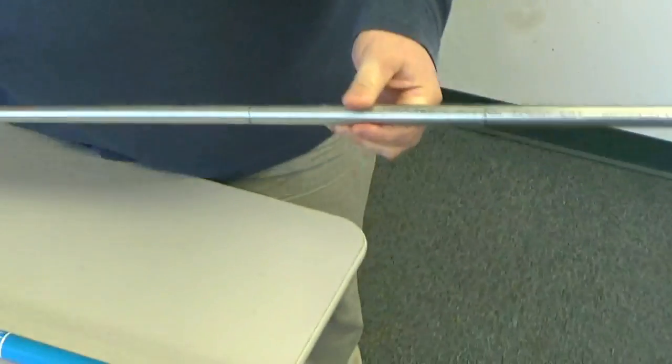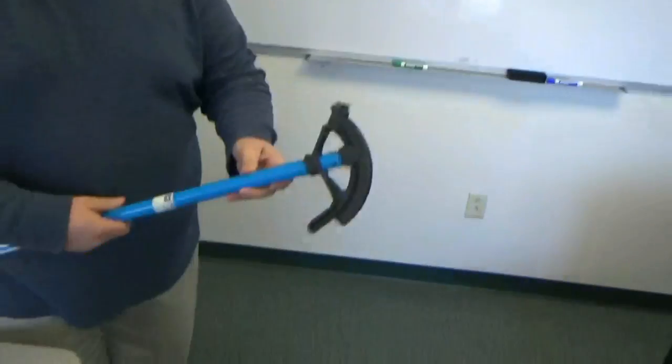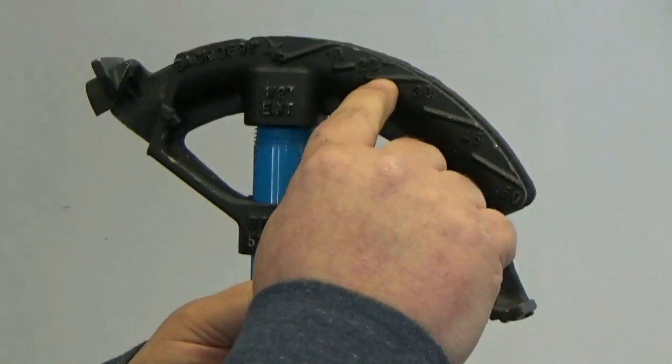Once we make our marks, we look at the bender. We're looking to do a 30 degree bend, so on our bender, we're looking to have the back of the pipe or the bottom of the pipe to be in line with this 30 degree mark.